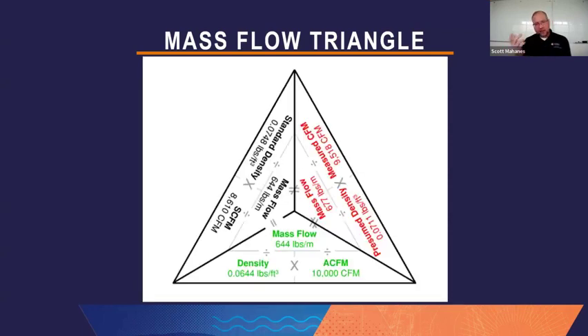Well, I kind of turned this into a tetrahedron now, with a third dimension on the third side, and the measured side of airflow now shows you what's really going to happen as a technician if I go out into the field and I go to measure for 10,000 CFM. Now, the goal is I have a 10,000 CFM design unit. I need to set the fan speed to 10,000 CFM. So as a technician, I go out there and I measure this 9518 CFM without a temperature probe on my DMM. And I need to compensate for the temperature, which happens to be 125 degrees. It's reheating to 125 degrees, let's say. By the way, this would be like 1,500 feet above sea level.